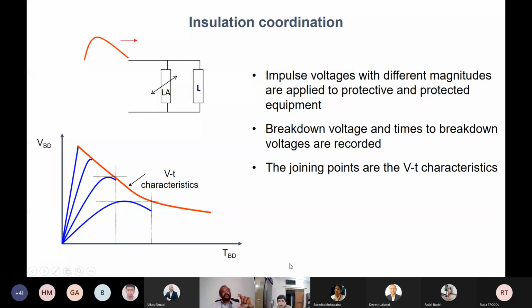Whenever you apply an impulse voltage with varying front time across anything, there will be a certain point of breakdown. And this breakdown voltage will be higher if the steepness of the voltage impulse is higher. Okay. And so if for various impulse wavefronts you get the breakdown voltage, you will get a curve like this.